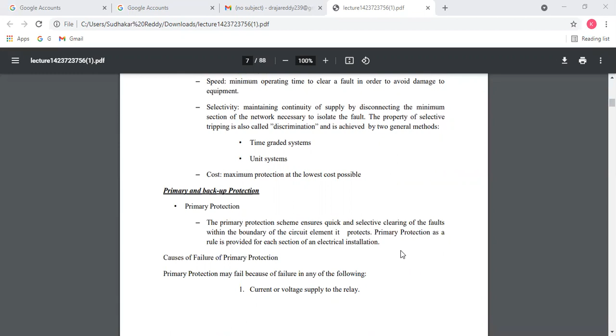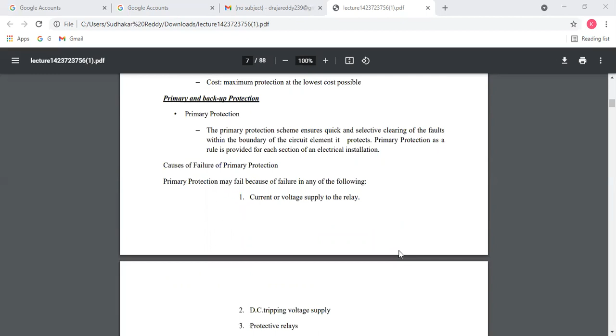Primary protection, as a rule, is provided for each section of an electrical installation. Primary protection will fail because of a failure in any one of the following. First, current and voltage supply to the relay. Second, DC tripping voltage supply. Third, protective relays. Fourth, tripping circuit. And fifth, circuit breakers. These are the main causes of failures in primary protection.